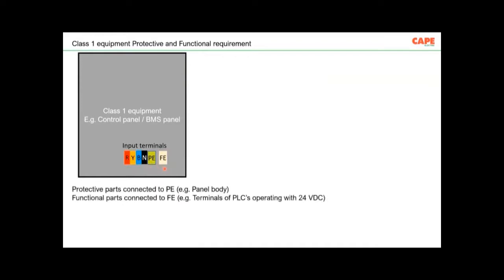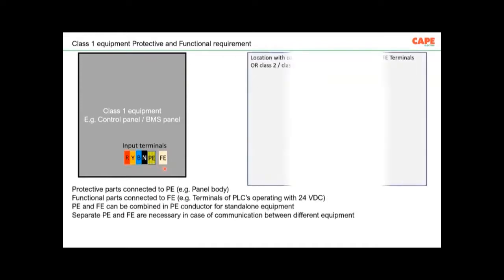Basically, a class 1 electrical equipment requiring functional PE and FE looks like this. It will have a 3-phase and neutral terminal, a protective earth terminal, and a functional earthing terminal. Now, the examples I have mentioned here.